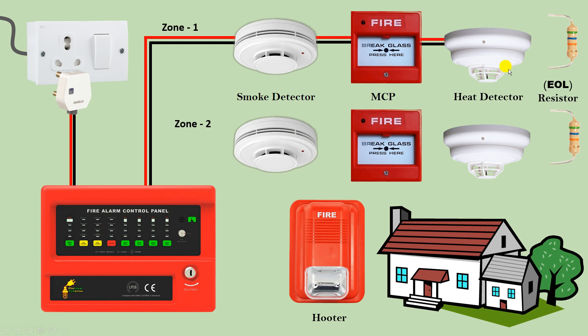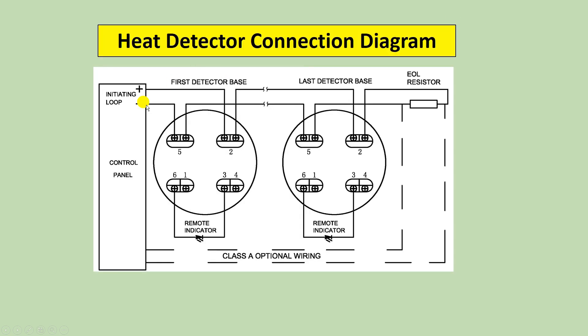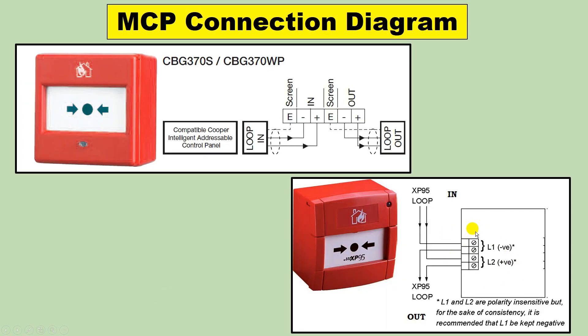Now take power supply from the MCP and provide it to the heat detector. In the heat detector also the connections are done in the same way — different numbered terminals are given. Connect negative power supply to negative and positive to positive terminal. Similarly, through looping of wire, provide power supply to the next device.